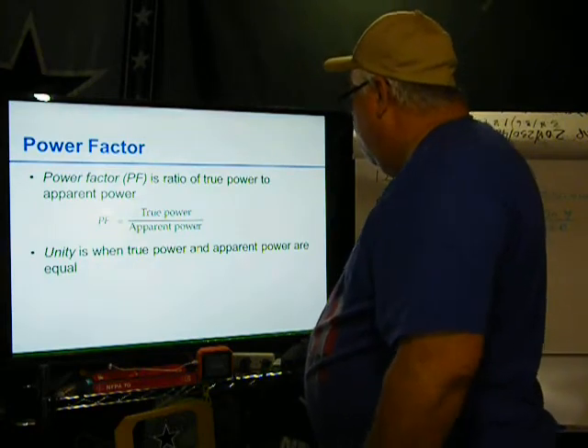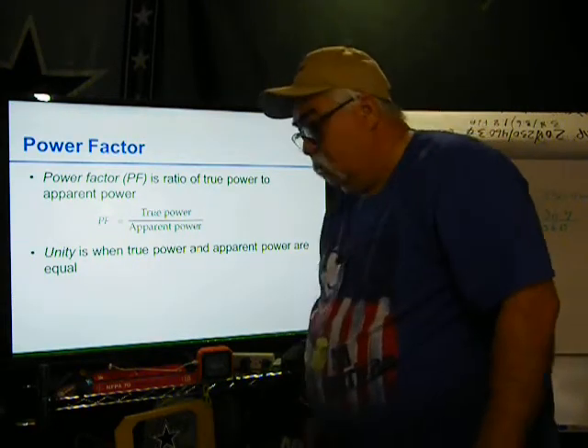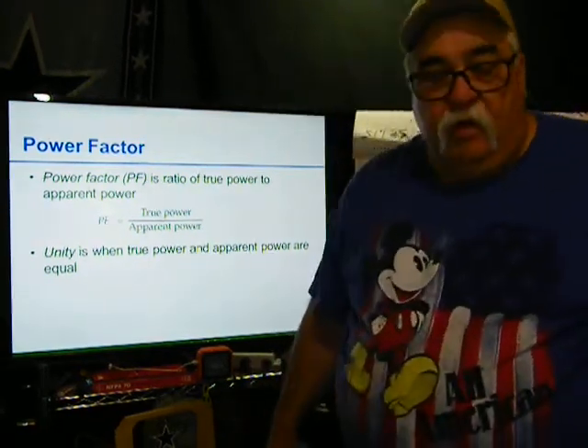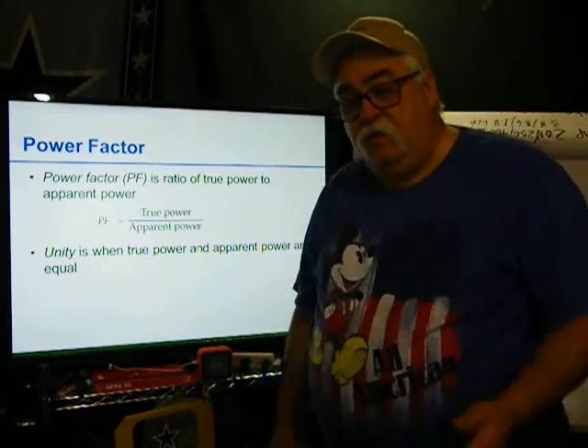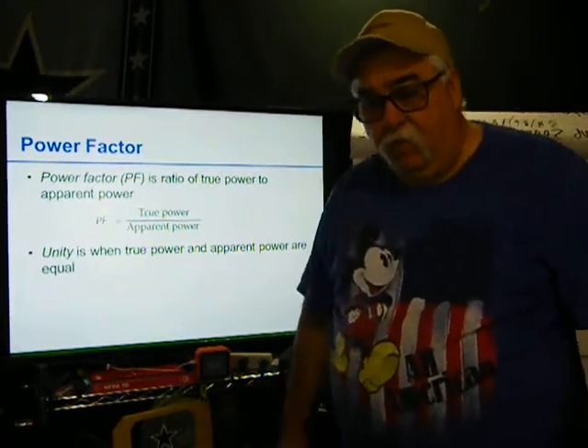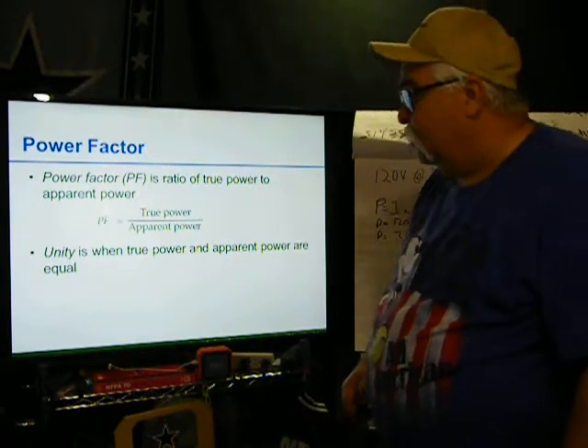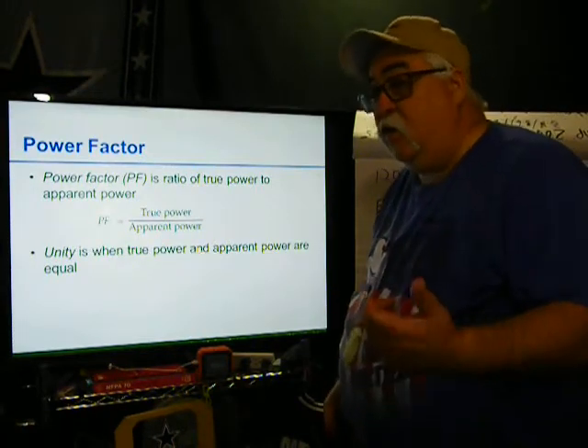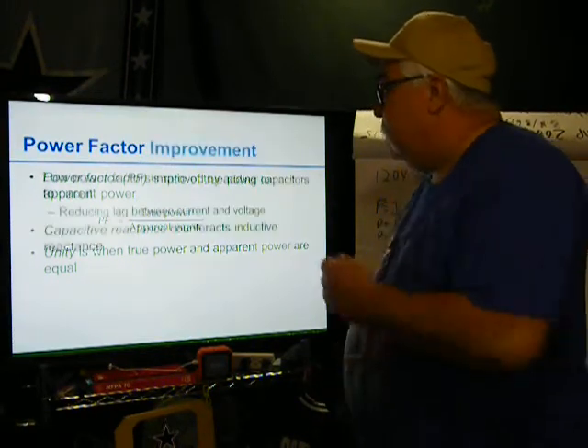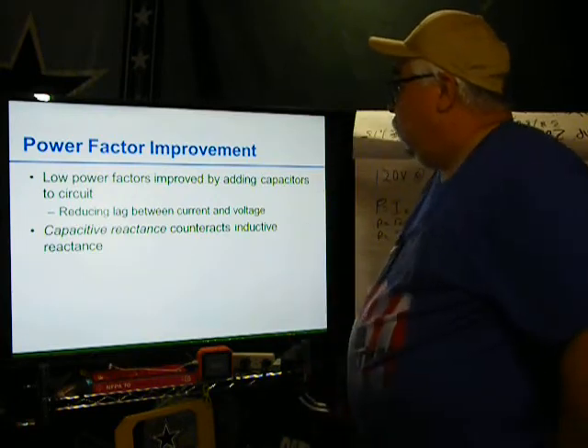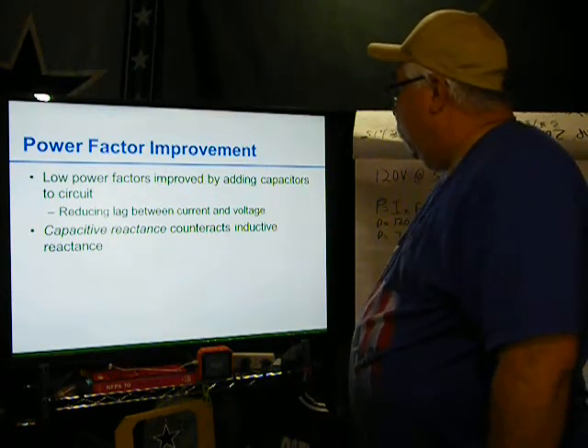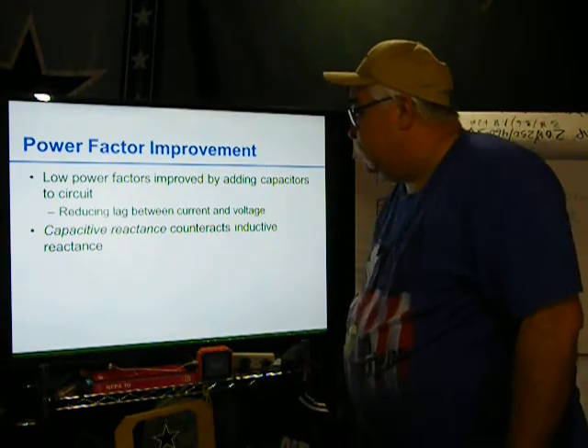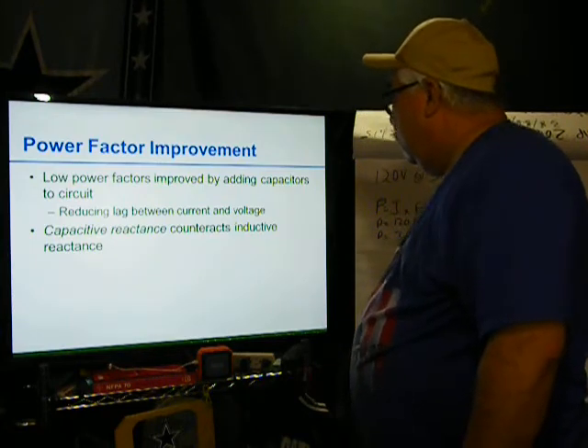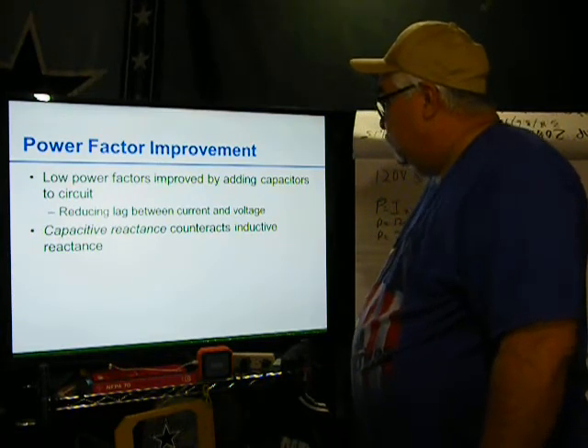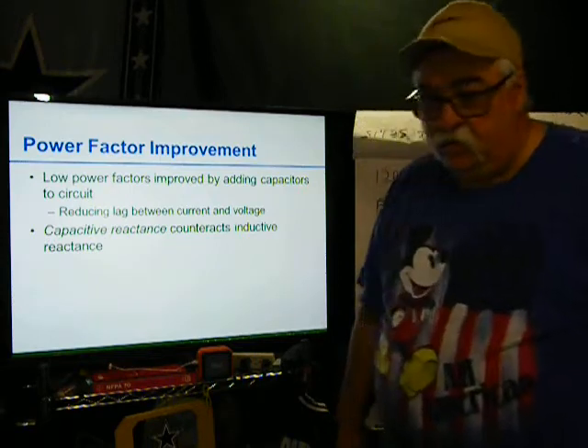Unity is when true power and apparent power are equal. So, in a perfect world, we want everything to be equal, but we don't have a perfect world. Electricity isn't perfect. But you can correct this. This can be corrected. Power factor improvement. Low power factor is improved by adding capacitors to the circuit, reducing the lag between the current and the voltage.